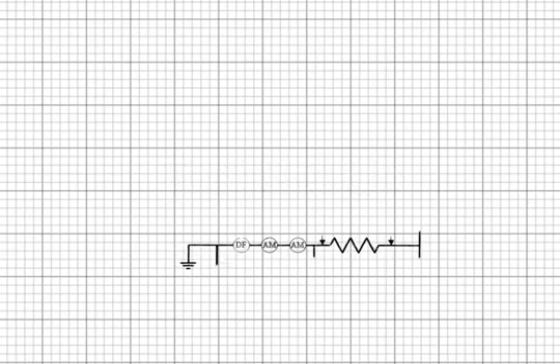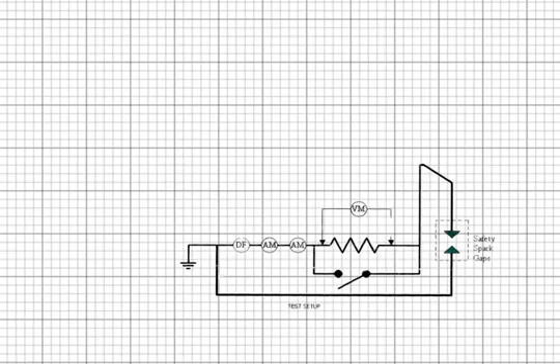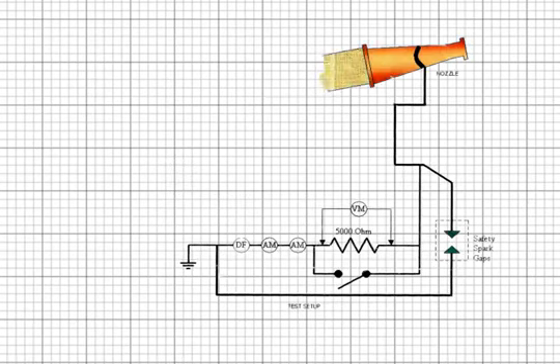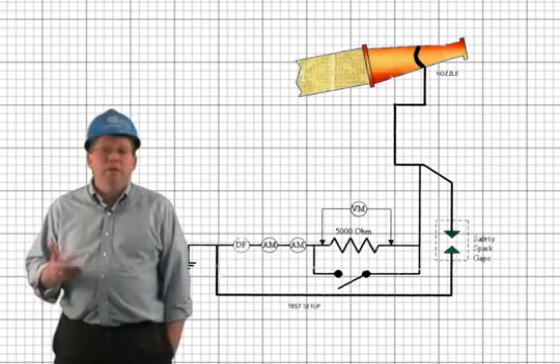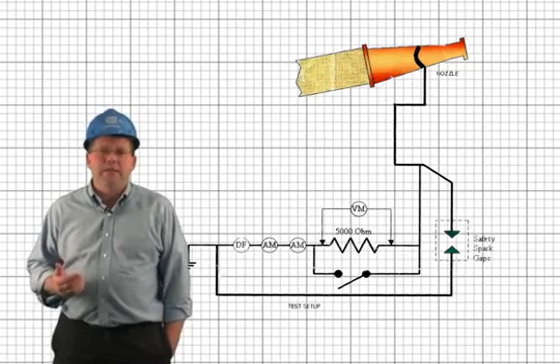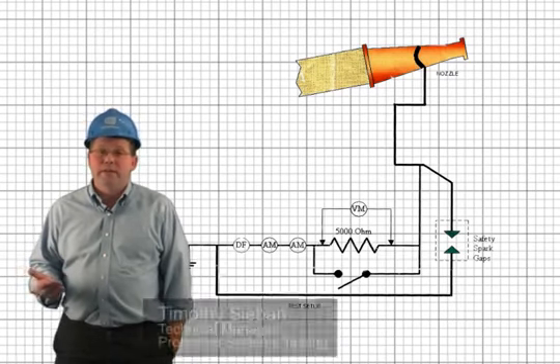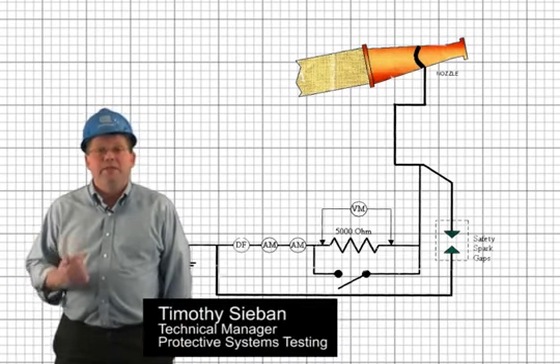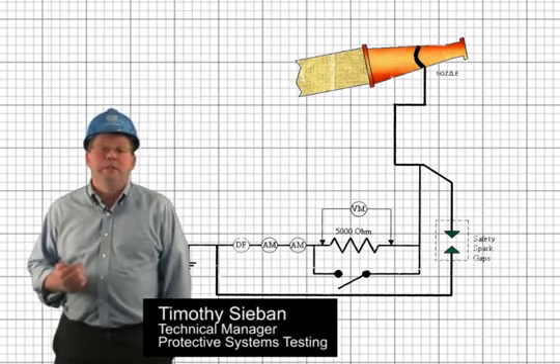For this test, it was my task to come up with the circuitry and equipment. With the field technicians, we connected up the equipment so that we could determine which distances was safe to spray the F500 concentrate and water mixture on live bus. My name is Tim Sieben, and I'm a technical manager for protective systems testing here at Con Edison's substation department.